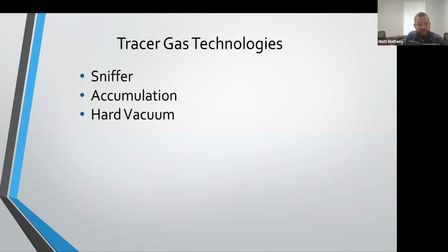It also offers something accumulation and hard vacuum do not: it not only tells you if you have a leak, it can pinpoint where the leak is. So not only can I tell if I have a leak on this weld joint, but by where the sniffer alarms as I move the probe, I can tell exactly where the leak is. That's sniffing in a nutshell.